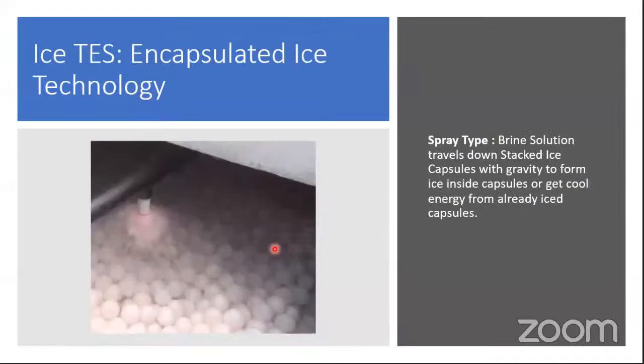Now, within the encapsulated ice technology, there is another technology which is ice spray technology, spray type technology. In this technology, the brine solution travels down over stacked ice capsules with gravity to form ice inside the capsules, or get cool energy from already formed ice. So ice capsules are here, and this brine solution is being sprayed over it. This is not a closed circuit; it is just being sprayed, and the brine falls down to the basin to contain the cool energy down there.